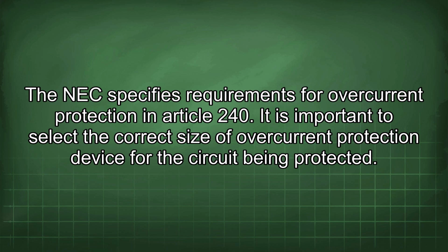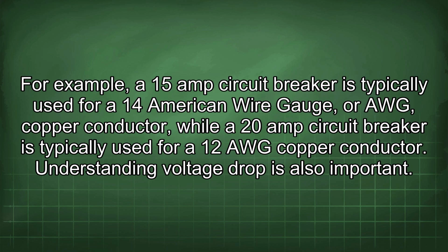It is important to select the correct size of overcurrent protection device for the circuit being protected. For example, a 15 amp circuit breaker is typically used for a 14 American wire gauge, or AWG, copper conductor, while a 20 amp circuit breaker is typically used for 12 AWG copper conductor.